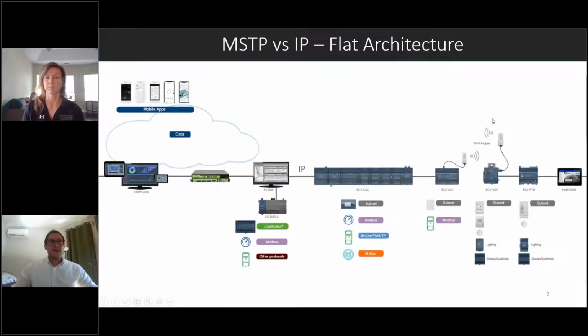Now taking a look at an IP architecture you could have - this is showing off what we like to call a flat IP architecture. This is definitely a strong preference for what I'd like to see in new facilities. Personally, I think this is the right approach - having not only your building level controller operating with BACnet IP, but all the other controllers within your site as well, being able to communicate that BACnet IP.